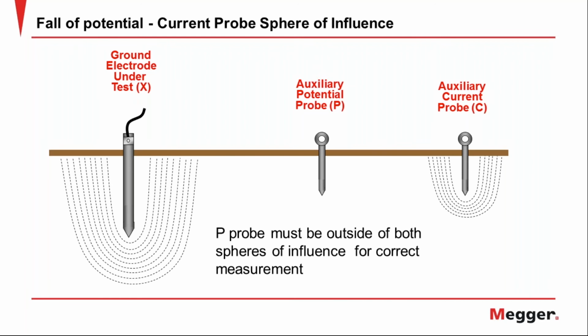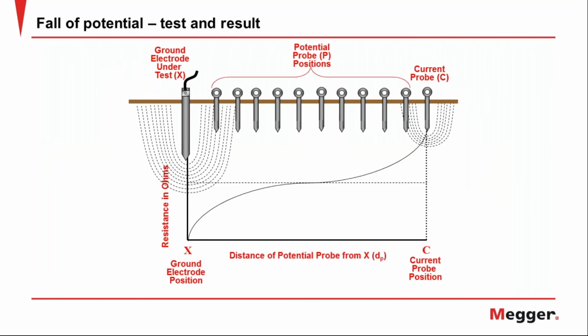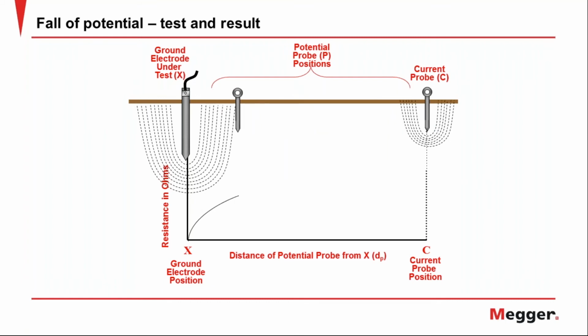So now, this is what you're going to result. You're going to graph this distance with resistance, and you're going to look for where that line flattens out. If that line flattens out at like 8 ohms, and you're supposed to meet a 5 ohm ground, you've got to drive more rods. If it flattens out at 2.5 ohms, you're good. Back up and you're good for now. So this is the way it works then.